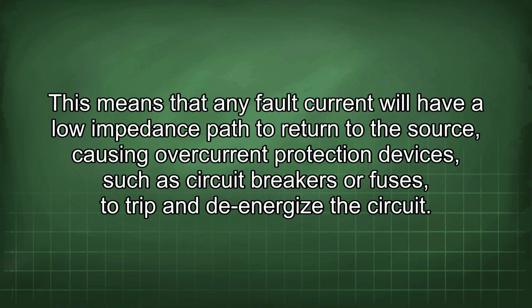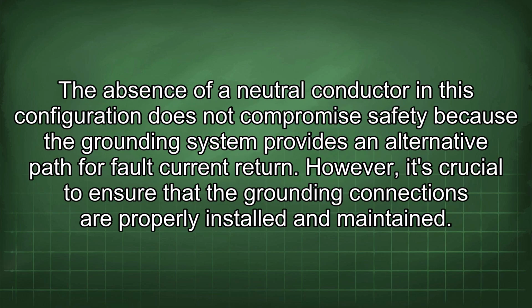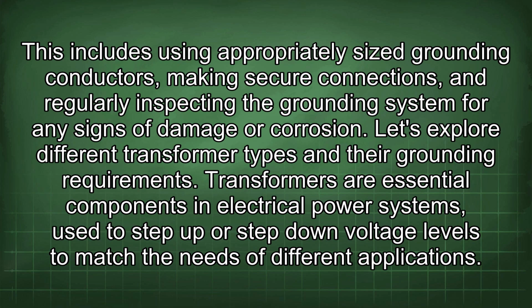This means that any fault current will have a low impedance path to return to the source, causing overcurrent protection devices, such as circuit breakers or fuses, to trip and de-energize the circuit. The absence of a neutral conductor in this configuration does not compromise safety because the grounding system provides an alternative path for fault current return. However, it's crucial to ensure that the grounding connections are properly installed and maintained. This includes using appropriately sized grounding conductors, making secure connections, and regularly inspecting the grounding system for any signs of damage or corrosion. Let's explore different transformer types and their grounding requirements.